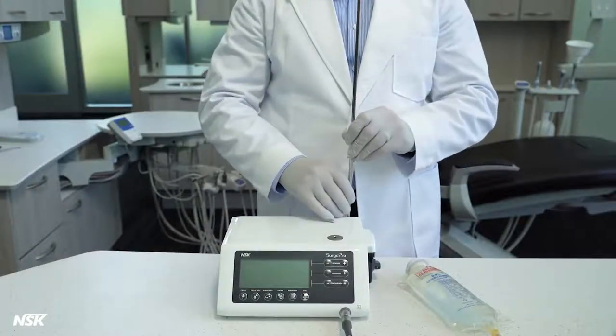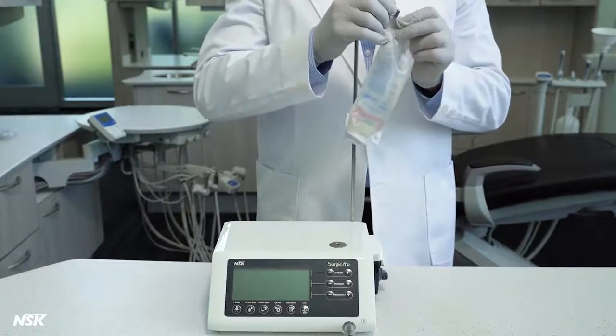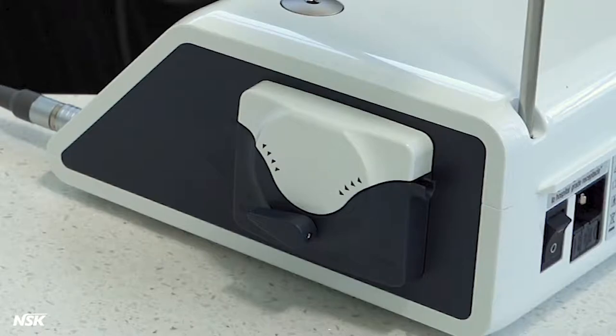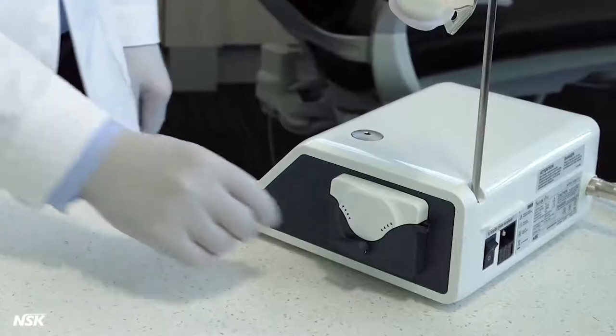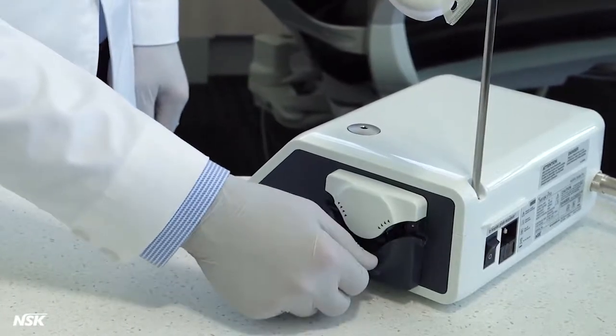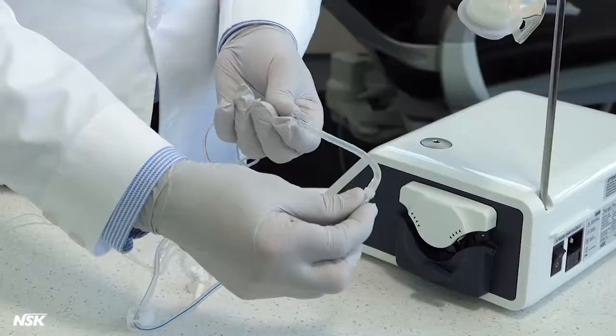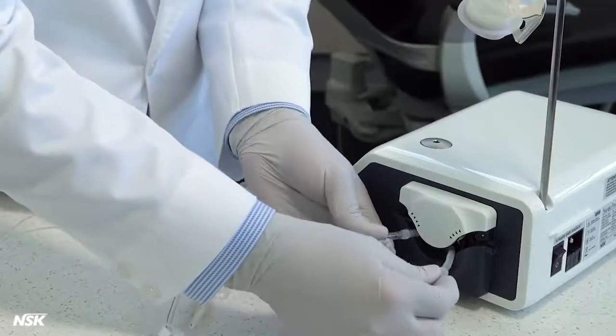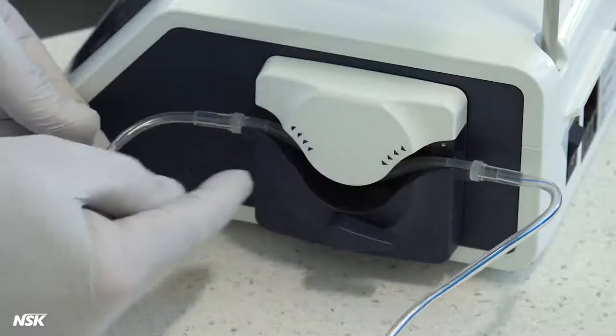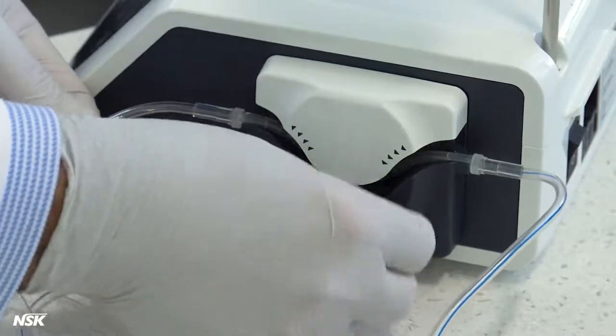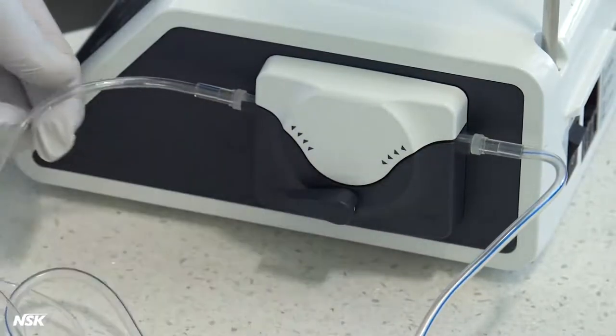Next, mount the coolant solution hanger post and hang the saline bag. To install the irrigation tube, be sure the lever of the pump is turned to open and the needle end of the tubing is facing toward the back of the unit. Then bend the tubing and insert inside the spindle. Make sure the two stoppers on the tubing stay outside the pump. Then turn the lever back to close.